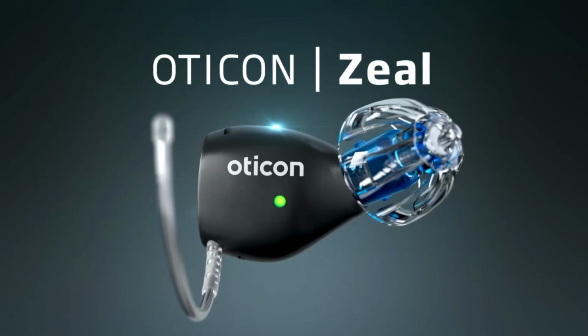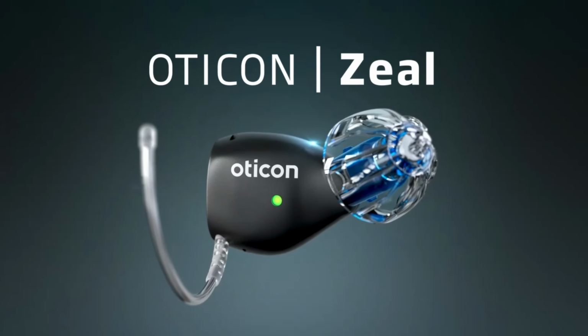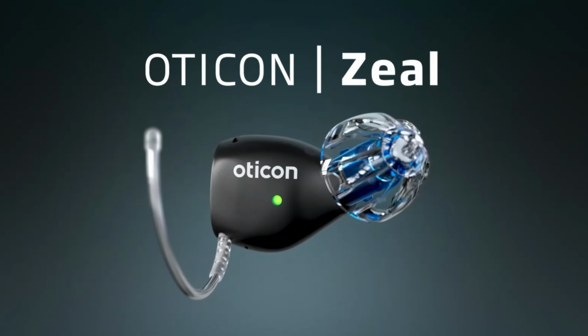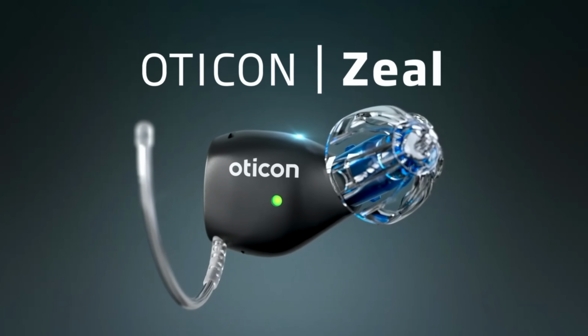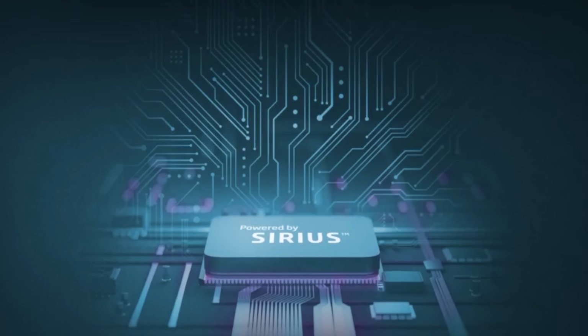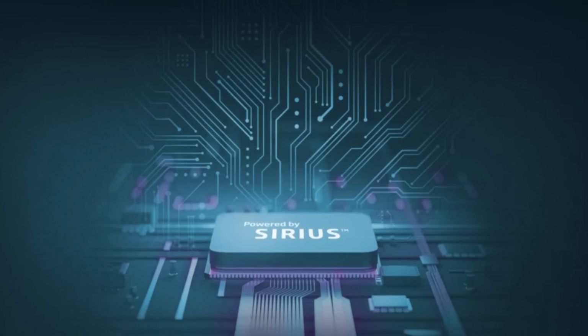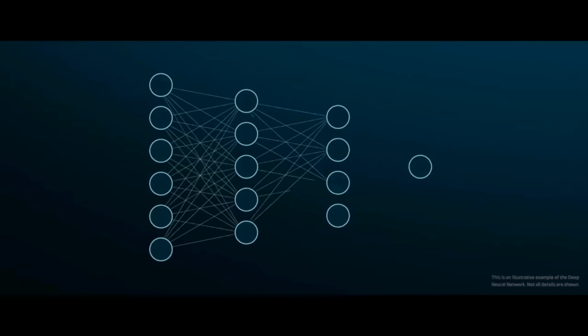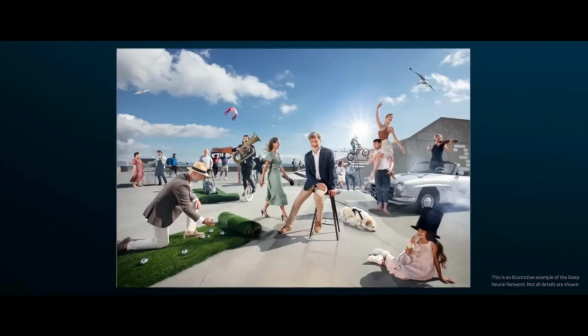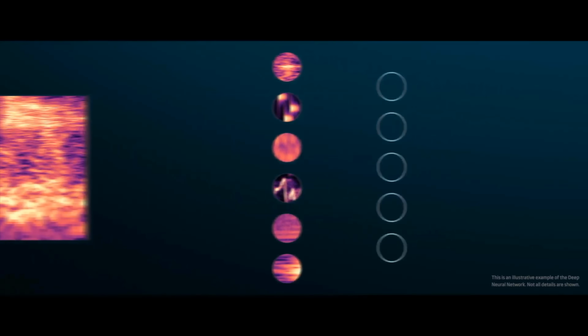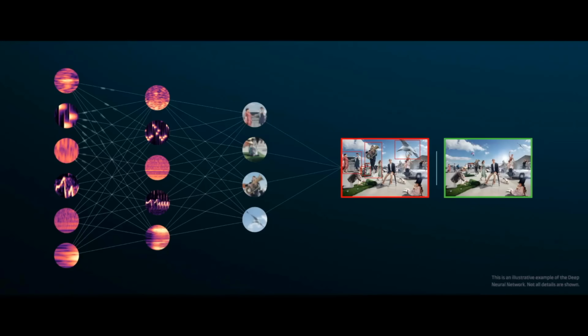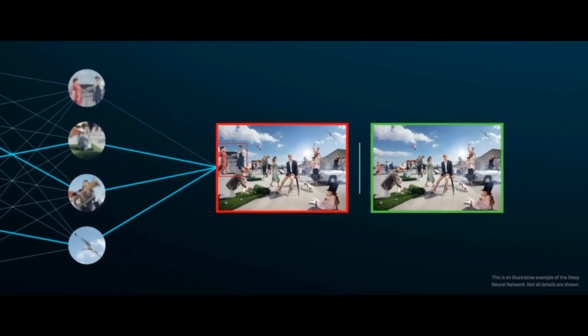First, let me cover some of the basics of this new hearing aid. The Zeal comes in Oticon's top-tier technology level, and it has a fixed receiver that can amplify for hearing losses up to 75 decibels. It uses the Sirius chip, which is trained with Oticon's second-generation deep neural network, which means that it uses the same always-on artificial intelligence sound processing and second-generation DNN-based noise reduction that you can find inside of the Oticon Intent hearing aid.